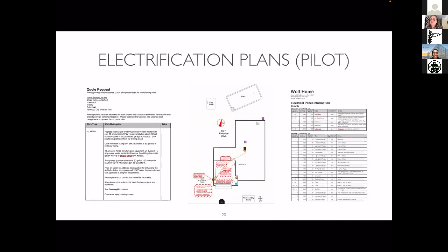15 amp water heaters are really important. The heat pump water heaters available, for example, at Home Depot, tend to be 30 amp heat pump water heaters. We like the 15 amp ones—they have a little less resistance backup heating capability, but they enable you to fit on the 100 amp panel.